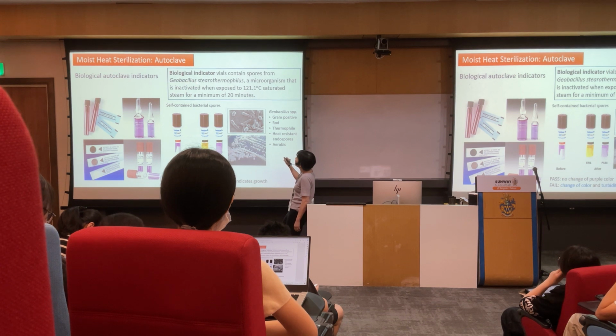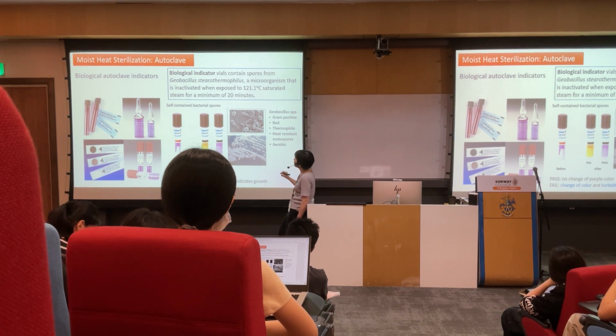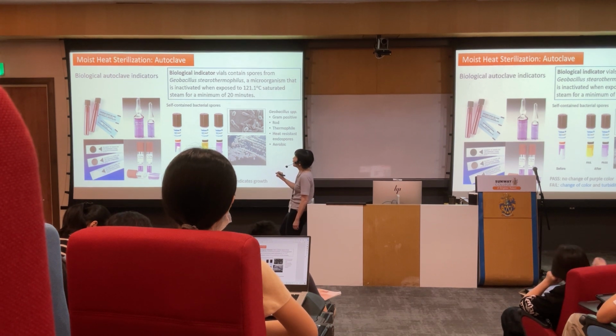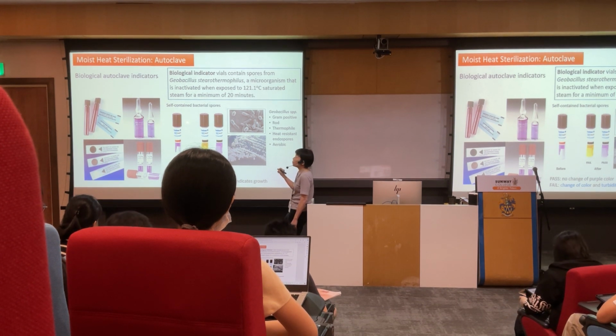This spore comes from Bacillus stearothermophilus. That is a microorganism, gram-positive bacteria, rod shape. They are thermophiles, meaning that they can endure high heat, and they form heat-resistant endospores. So normally, below 100 degrees Celsius, you may not be able to remove the endospore. Now, they're putting the spore inside, and they also have the pH indicator, so it's purple color. Then they put this tube together with whatever you want to autoclave into the autoclave, the machine.